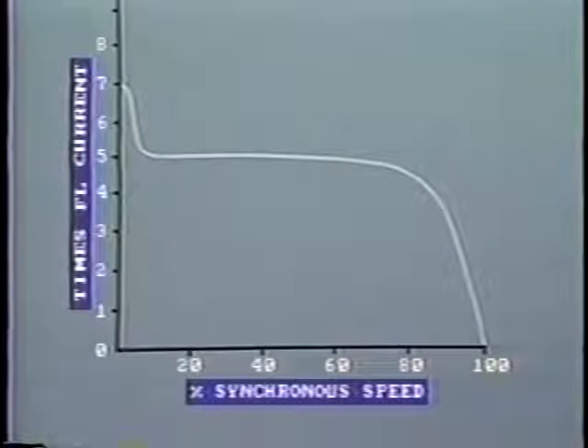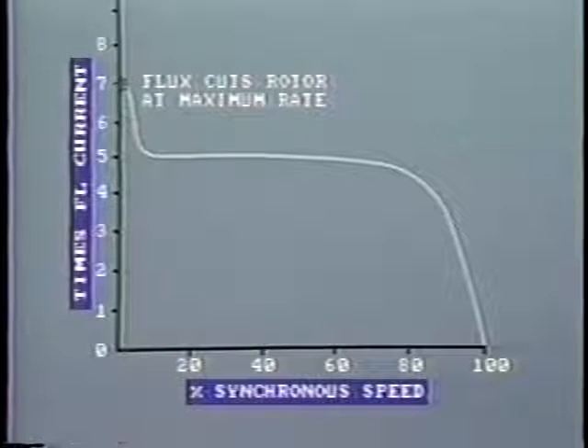Let's look at the startup curve for a motor which is driving a large boiler fan. Plotted along the bottom, we indicate speed in terms of percent synchronous speed. Here on the vertical axis, we have stator current. When the stator winding is first energized, the rotor is stationary, so a very large current is induced into the rotor conductors as the rate of cutting by the rotating flux is maximum. Correspondingly, a very large stator current is drawn, perhaps 7 times full load current.